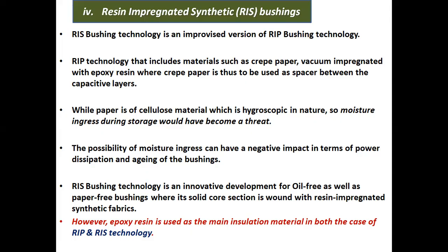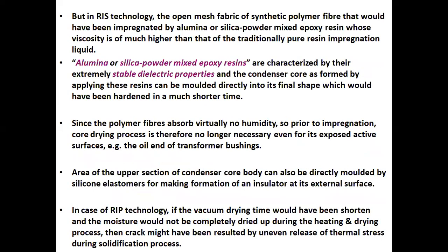However, epoxy resin is used as the main insulation material in both resin impregnated paper as well as resin impregnated synthetic technology. But in RIS technology, the open mesh fabric of synthetic polymer fiber is impregnated with alumina or silica powder mixed epoxy resin, whose viscosity is much higher than that of the traditional pure resin impregnation liquid.